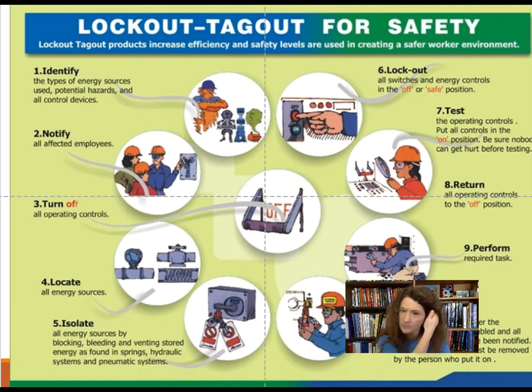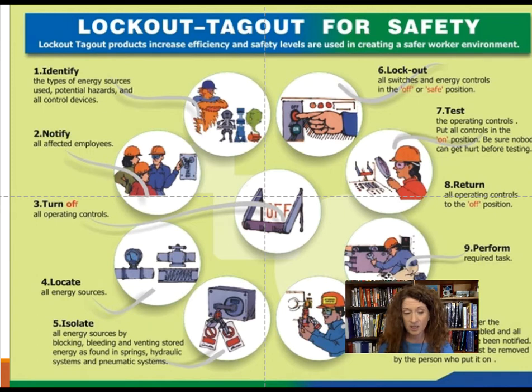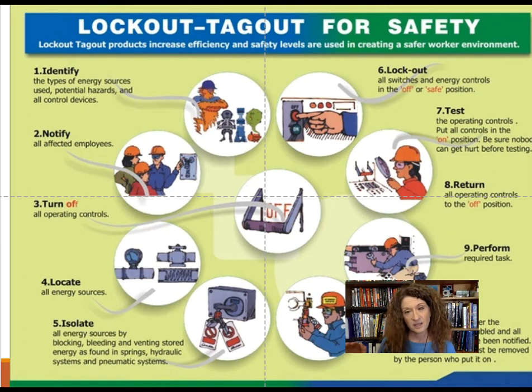Step 8: After testing, put the switch back in the off position — even if it didn't energize — so that when you finally do turn it on, it won't already be in the on position. Think of it like a light switch: you turn it off, cut the power, lock it out, try turning the switch on, and if the light doesn't come on, you're good. Then turn that switch back off. That is step 8.